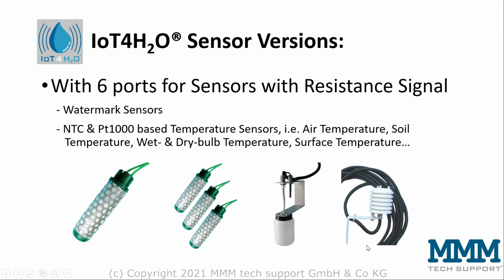IoT for Water sensor versions: we have several versions for different sensors. The first version has 6 ports for sensors with resistance signal. This includes watermark sensors, but also temperature sensors based on NTC or PT1000 thermistors, which could be an air temperature, a soil temperature, a wet and dry bulb temperature, a surface temperature, or any other temperature you would need.